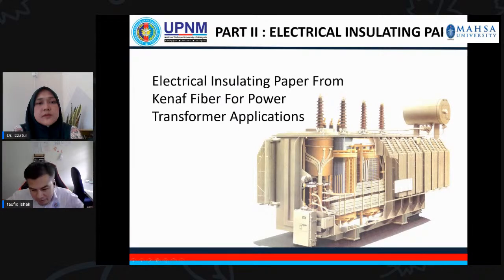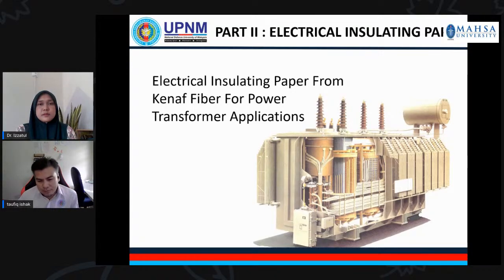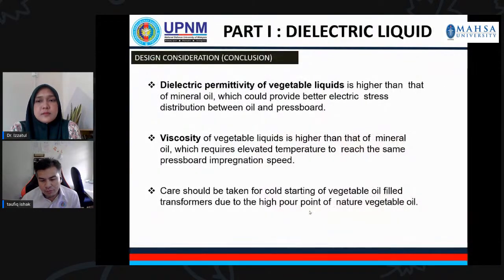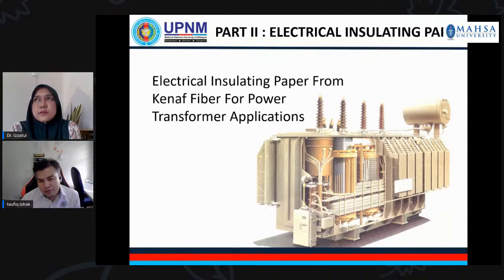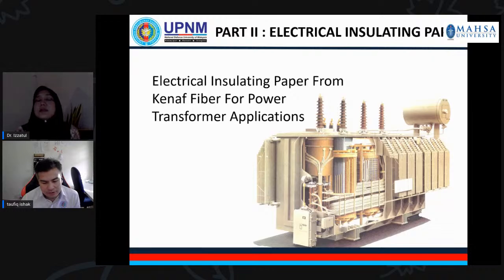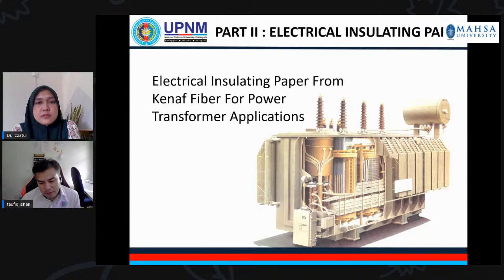This part is regarding the solid insulation, or you can call it electrical insulation paper. In this study, I try to develop a new kind of insulation paper, made from Kenaf fiber, for power transformer application. For your information, the insulation paper and pressboard inside the transformer is generally made from softwood pulp, which has been used for decades, maybe since the beginning of the transformer. This insulation paper is not only used to wrap the copper conductor, it is also used as a support of the winding. As you can see here, this is the paper insulation, and this is pressboard. It gives the support for the winding of the transformer.